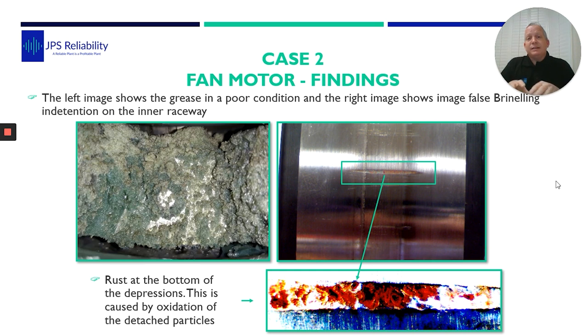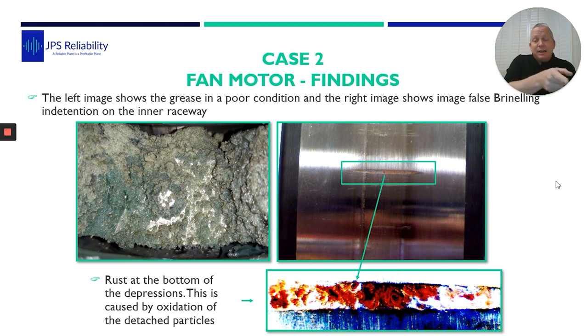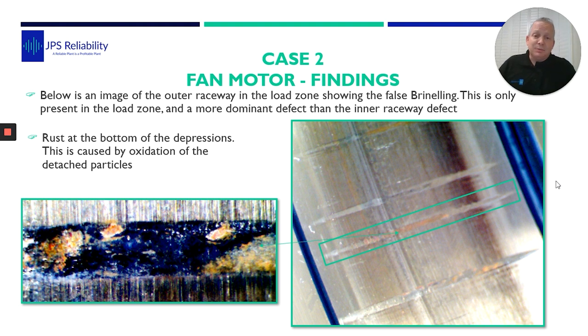They shut the fan down in a controlled situation, took the bearing out, and we went to have a look. On the left hand side of the screen you can see the grease — the grease is contaminated and starting to separate within itself. There is also a picture of the inner race where you can see a mark on it; when we looked under the microscope it's actually a crush on it, so we can see that's false brinelling. But the damage was worse on the outer race. When we looked at the outer race, these dents were like craters — you could feel them.